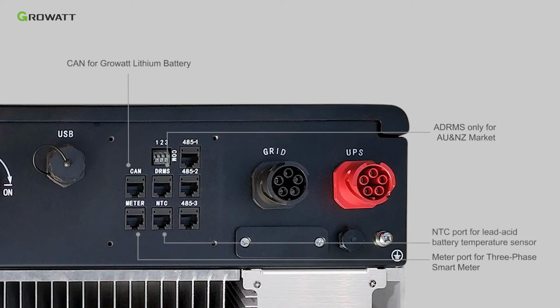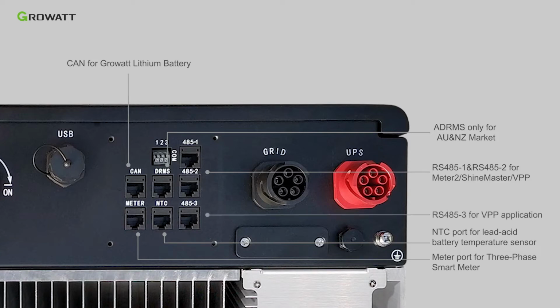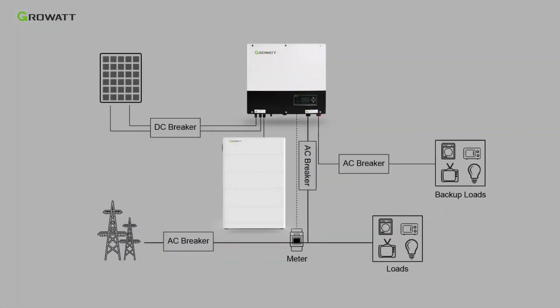NTC port for the lead-acid battery temperature sensor, RS485-1 and RS485-2 are used as meter 2 for the application of AC coupled, or ShineMaster to support the application of multiple SPH in parallel. RS485-3 is used for VPP application. And please follow the system diagram to do the whole system installation.